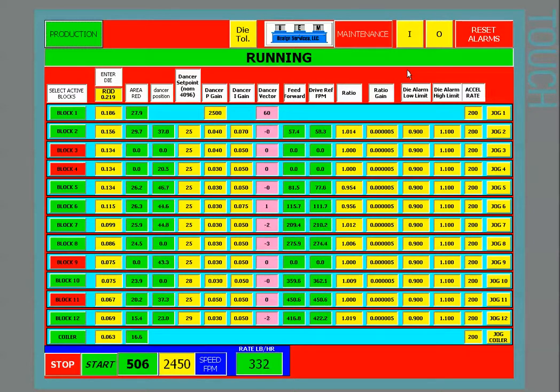This also provides you with all the trims for the dancer control gains, and then the high-low limits for the alarms, for the ratio alarms, for the die tolerance calculator. And then it gives you the accel rate for the drive, for each individual drive as it's jogged. We also have jog buttons to the right side that allow you to manually jog it from the screen.